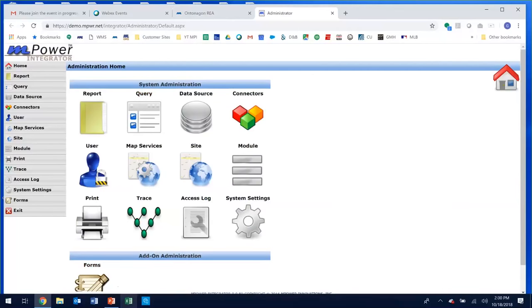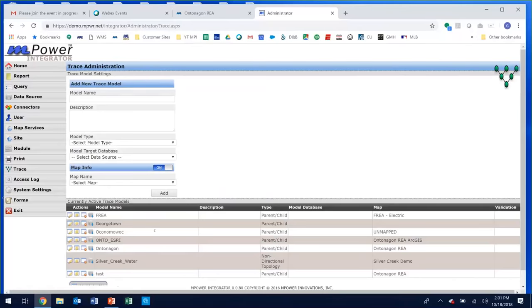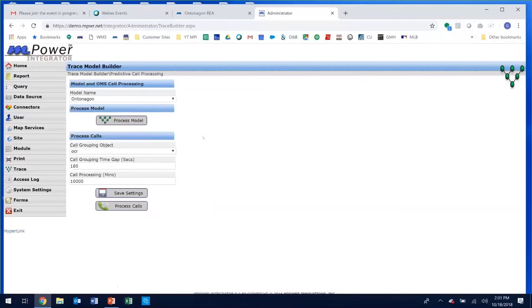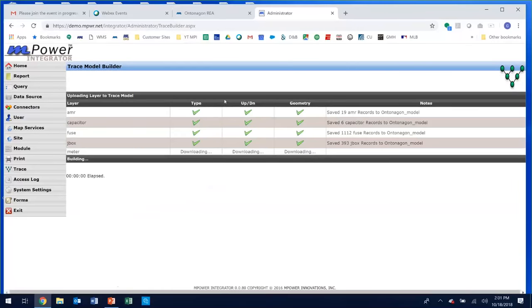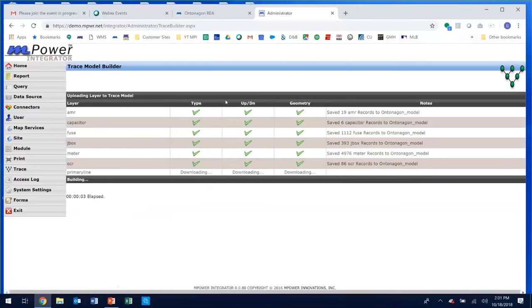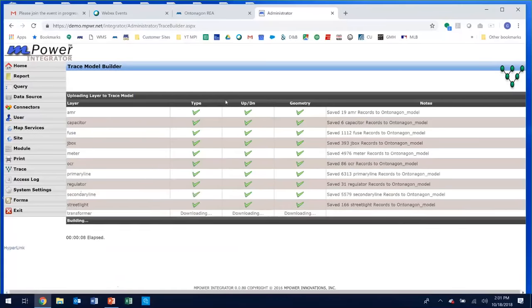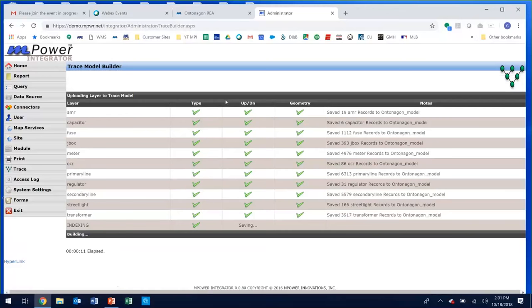And then once you have your maps up to date, with the circuit model flowing correctly, you want to be able to maintain that. If you use a product like Milsoft or CYME, you want to be able to keep that updated. And really where that should take place is inside your maps. That's where the work should be done. So I'm going to go into our trace module here, and into the model for this particular utility. And what I'm going to do is run process model. This is something you would do anytime there have been changes to the map. You want to periodically check and make sure that your parent-child data model, the standard for electrical, doesn't contain a mistake, so that when we really need this model during an outage, we can count on it being correct.